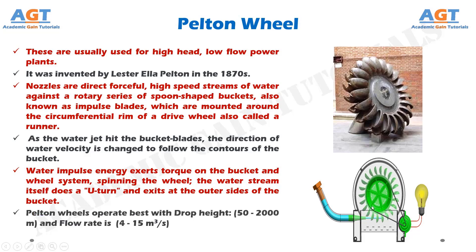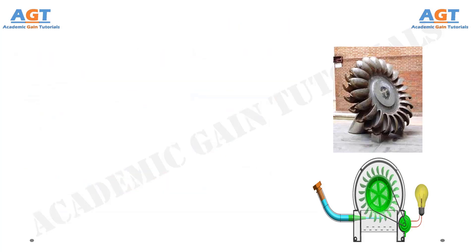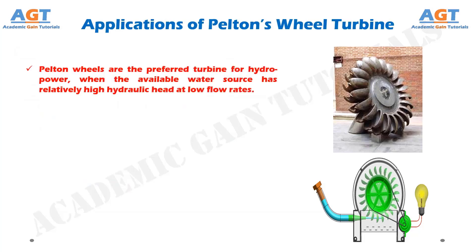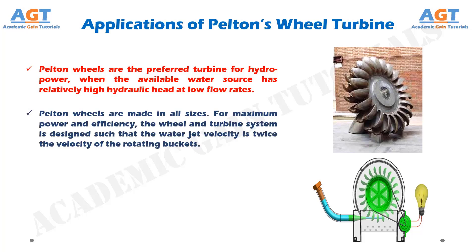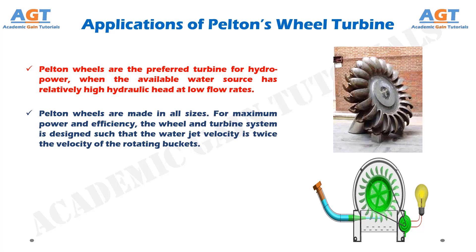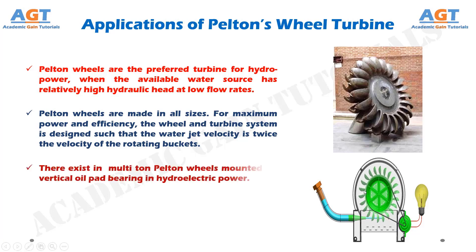Pelton wheels operate best with a drop height of 50 to 2000 meters and a flow rate of 4 to 15 cubic meters per second. Pelton wheels are the preferred turbine for hydropower when the available water source has relatively high hydraulic head at low flow rates. For maximum power and efficiency, the wheel and turbine system is designed such that the water jet velocity is twice the velocity of the rotating buckets. Large multi-ton Pelton wheels are mounted on vertical oil pad bearings in hydroelectric power plants.